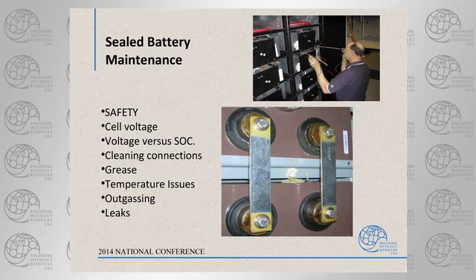So what do we have? We've got connection issues again that we've got to look at, and this is some No-Ox on them. And this is a UPS string, again 540 volt DC. What do you notice with the technician checking voltages? No face shield. Yeah, and he's pushing voltage probes all the way back here.